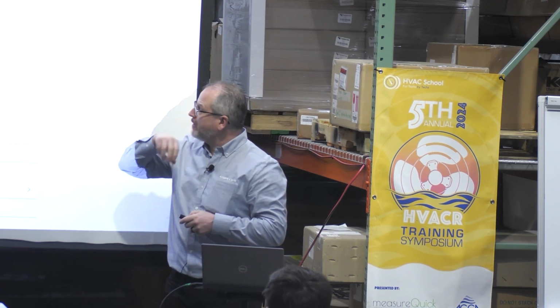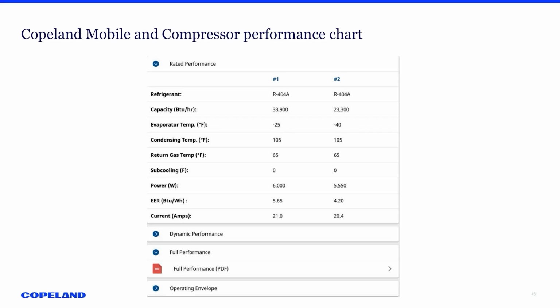So in this example, we have a couple of different rated performances, but we're going to concentrate on the left side. We have an evap temp of -25 and a condensing temp of 105, right? In here, you can also look at our amp draw at this, what it's running at right now, would be 21 amps. That's what we want to see.